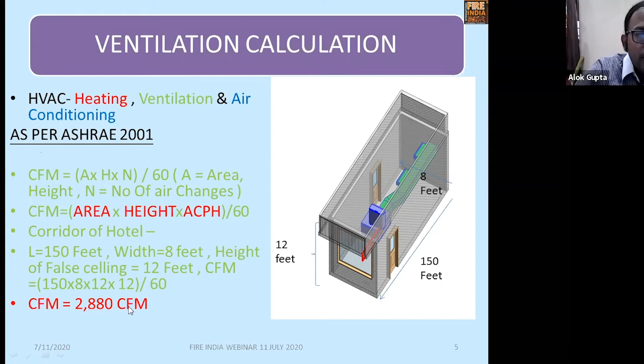A similar amount of air we have to pump in, and a similar amount we have to exhaust. So the exhaust calculation will be 2880 CFM, and the supply as well. We generally feel like a particular room is on positive pressure, so let's understand what positive and negative pressure mean.